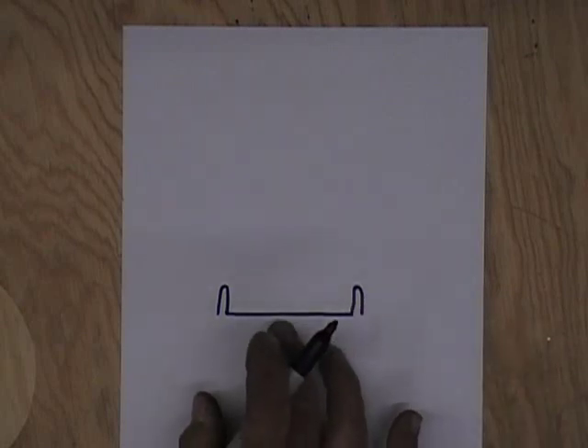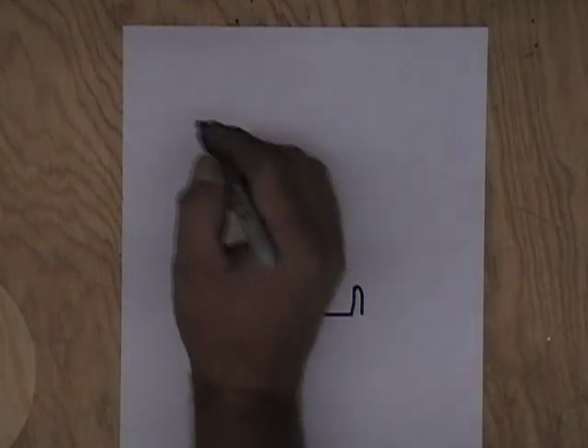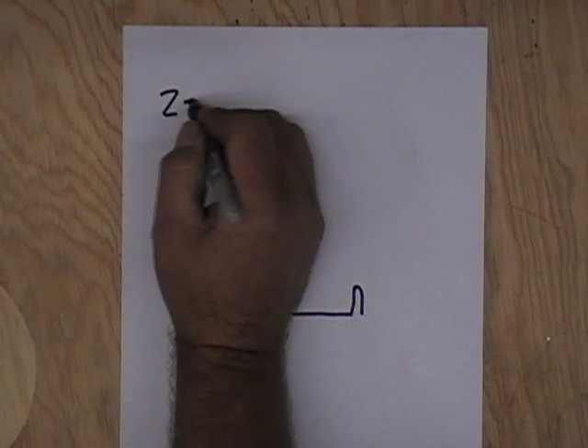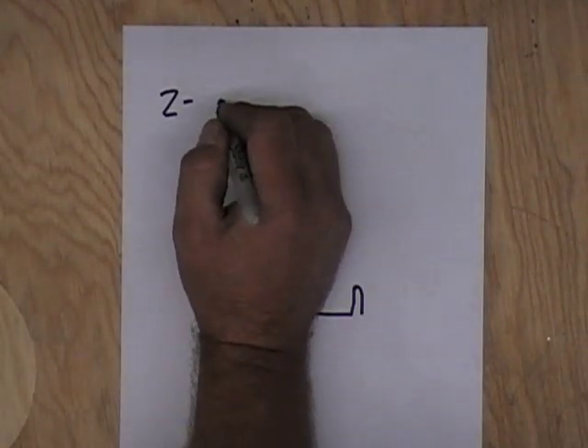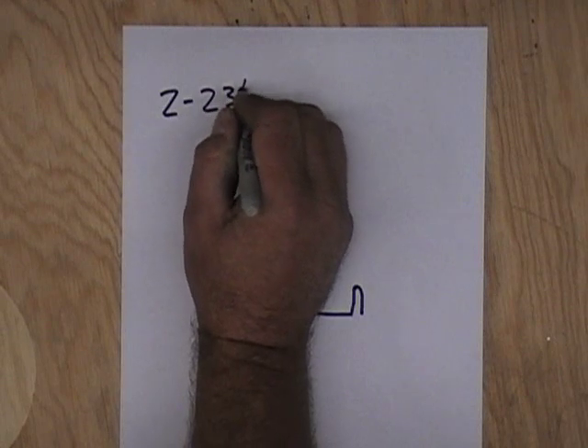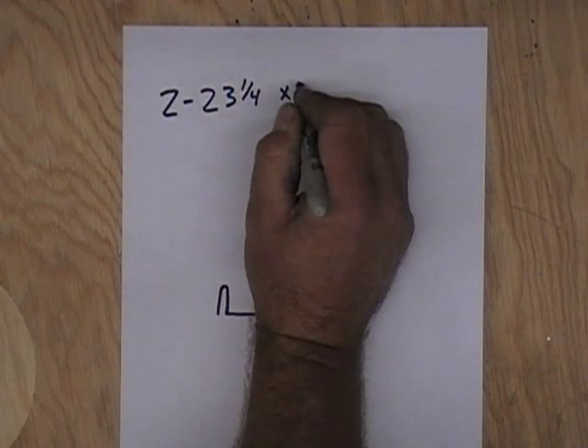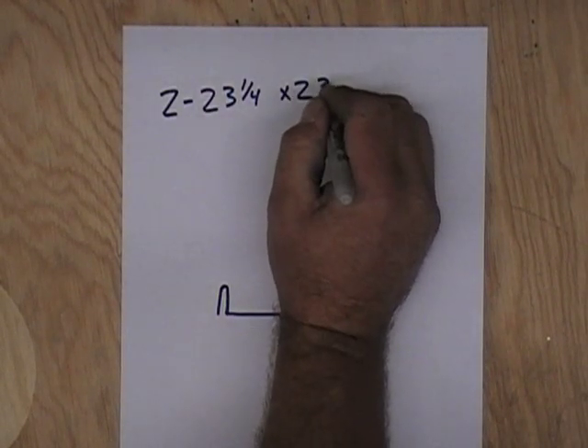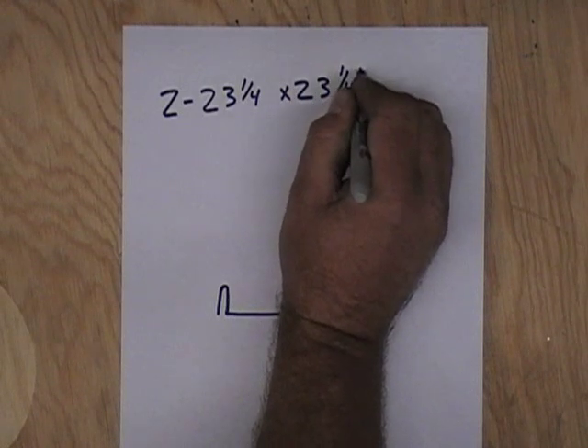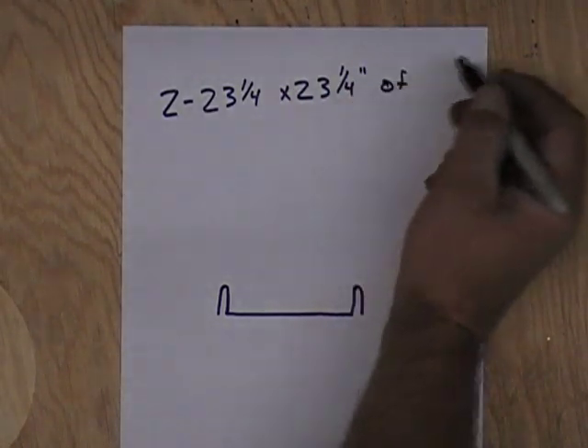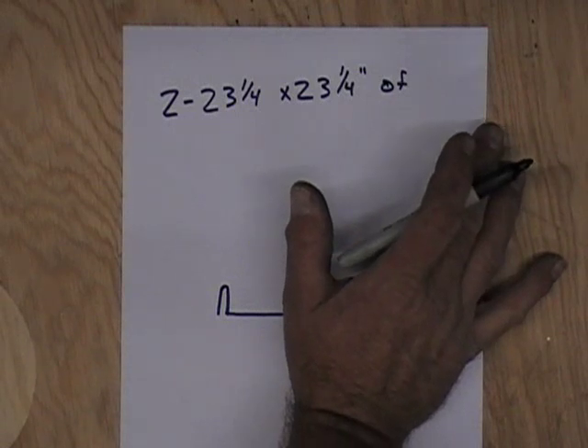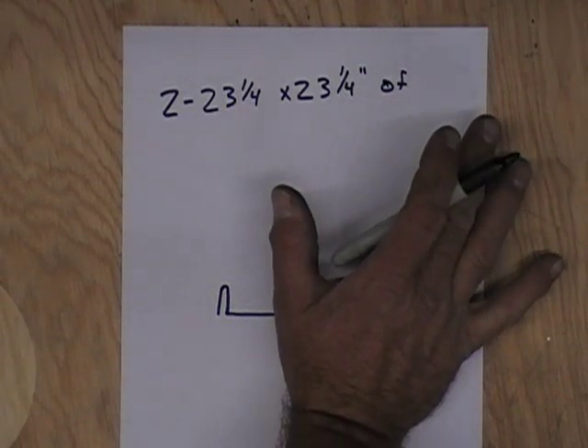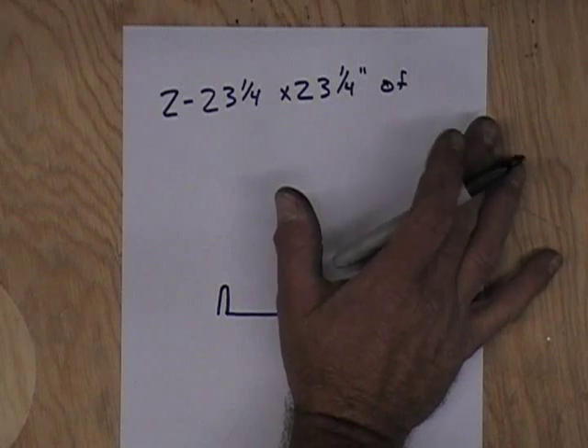Now this is going to actually be bent on all sides, and so since we need a top and a bottom to this, we need two of them at 23 and a quarter by 23 and a quarter inches. And this time, we want to use 24 gauge, and the reason is that there's going to be a lot of weight on these. The 26 gauge isn't going to hold up as well.